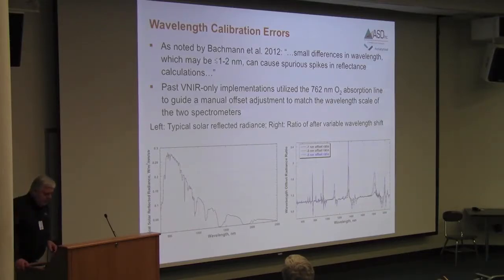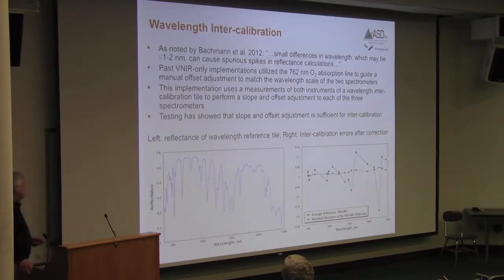So what we ended up with for this system was we still use the atomic emission lines to calibrate the individual spectrometers, but in the field, right before you make your field measurements, you view this reference tile that has a glaze that has a mix of a couple different rare earth oxides in it, and then it also has a piece of mylar at the top.